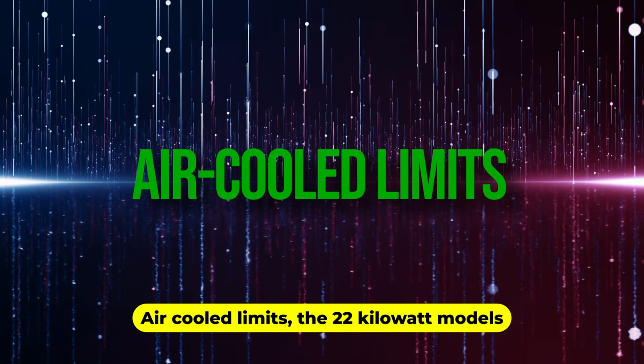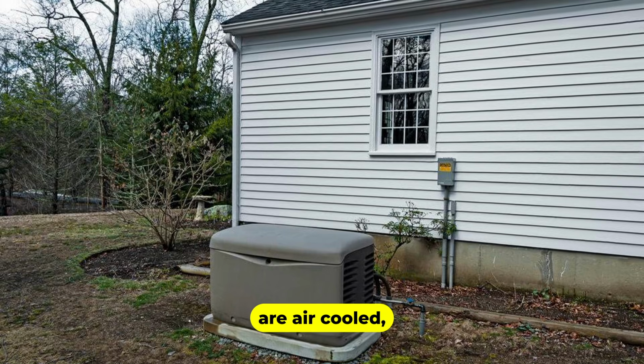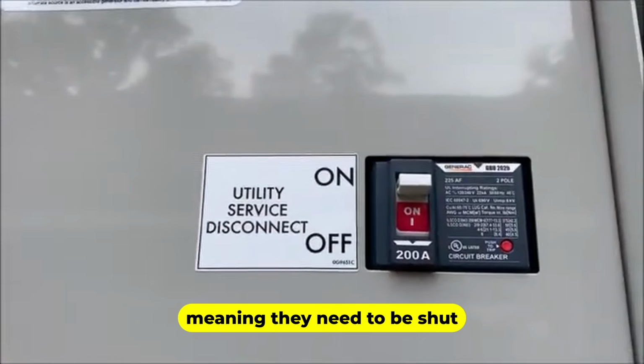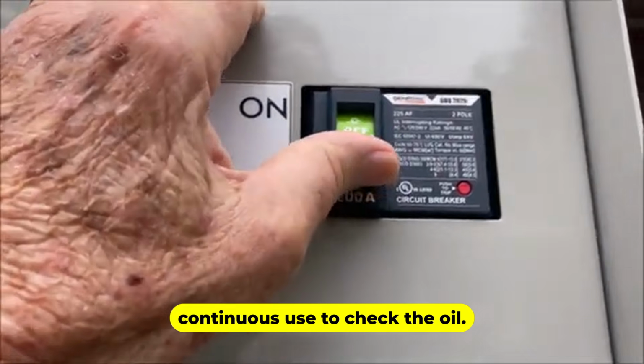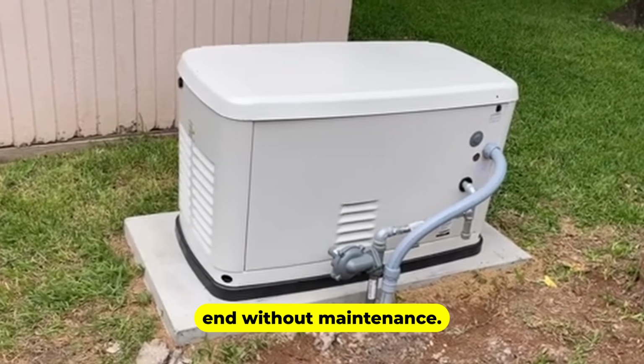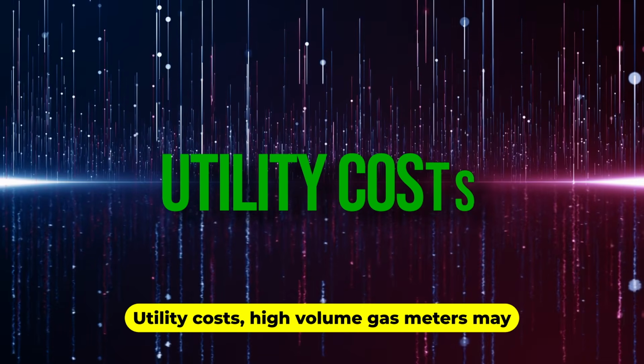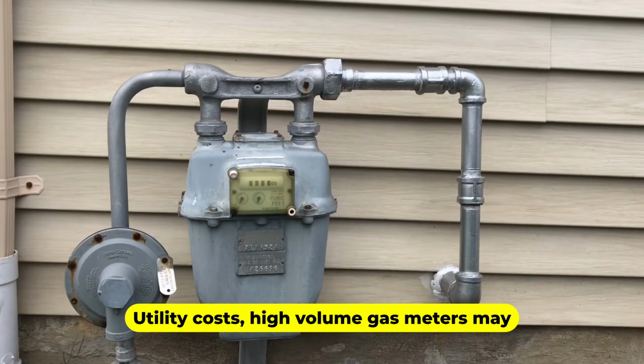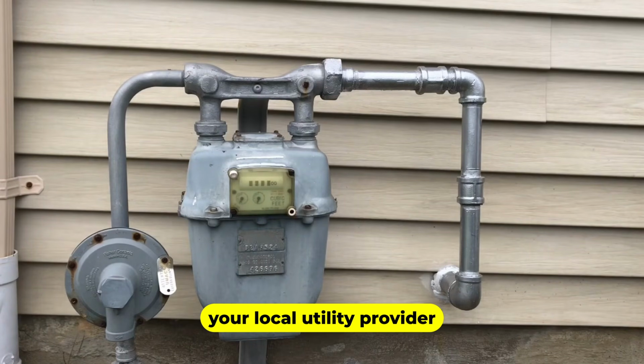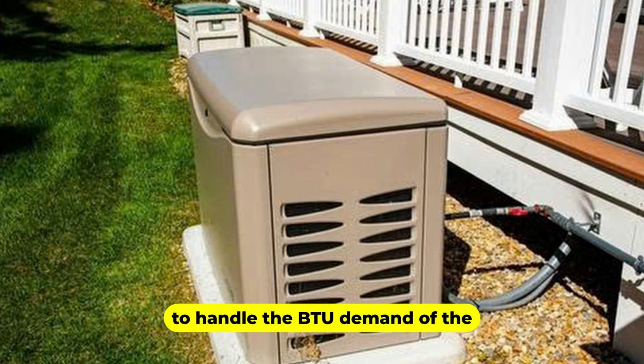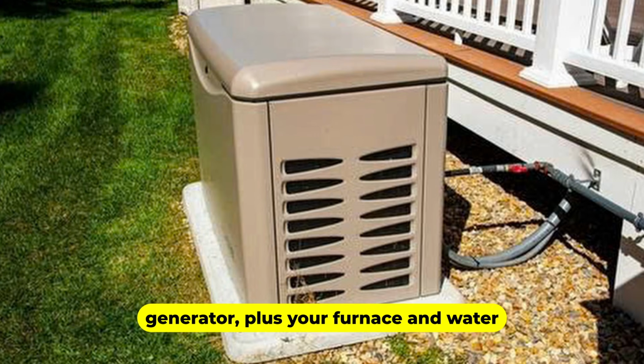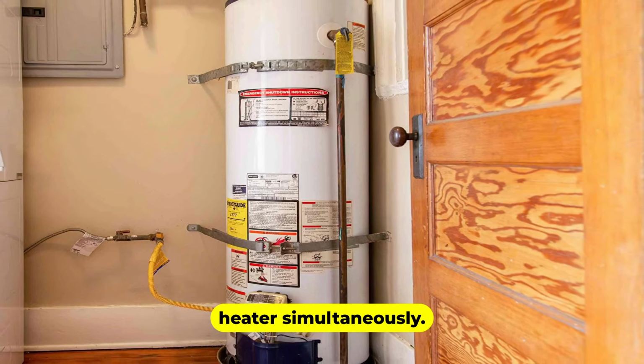Air-cooled limits. The 22 kilowatt models are air-cooled, meaning they need to be shut down every 24 hours of continuous use to check the oil. They aren't intended to run for weeks on end without maintenance. Utility costs. High-volume gas meters may need an upgrade from your local utility provider to handle the BTU demand of the generator, plus your furnace and water heater simultaneously.